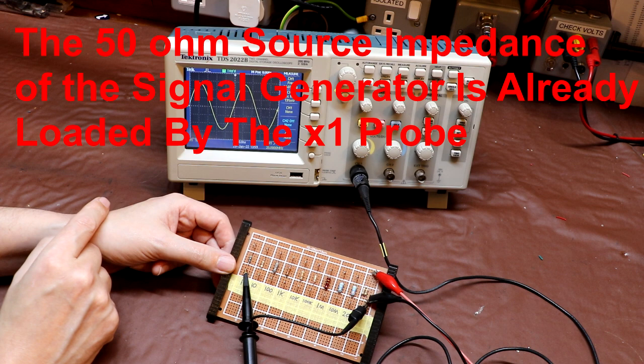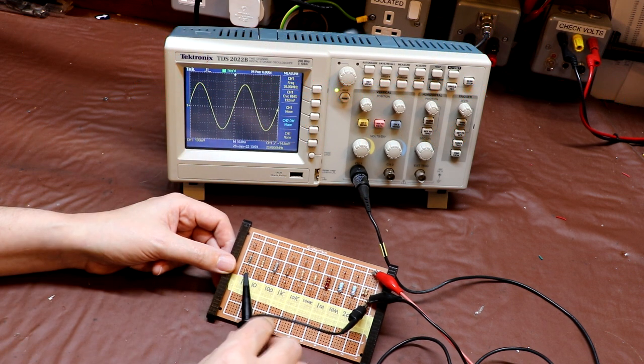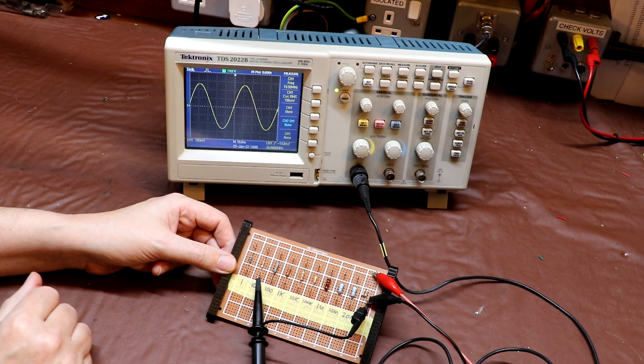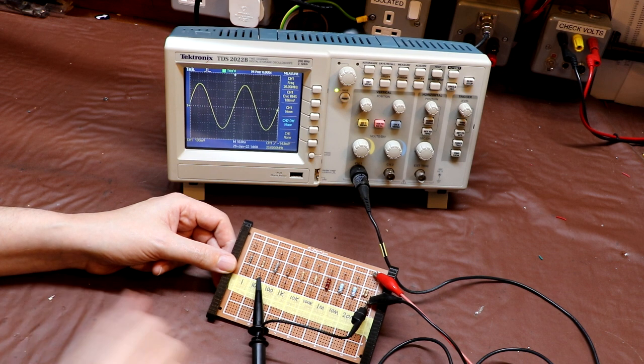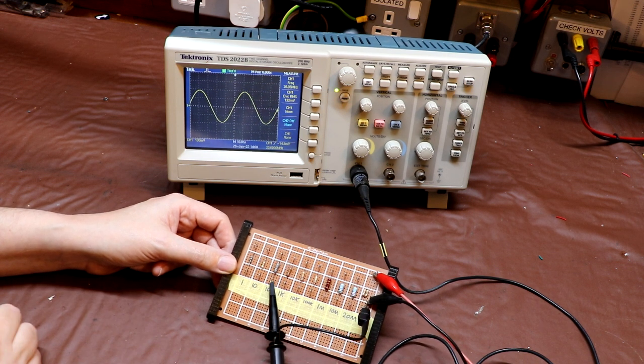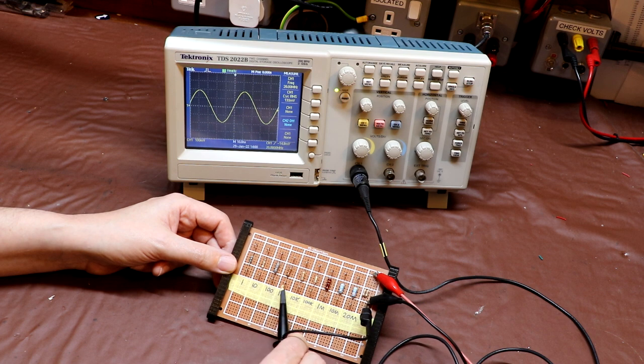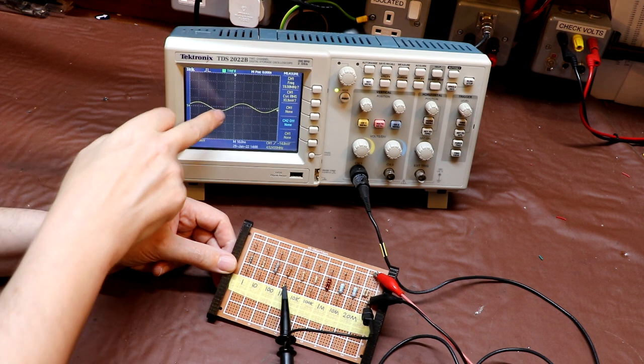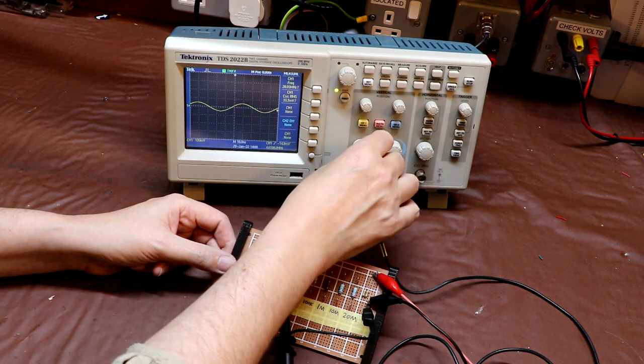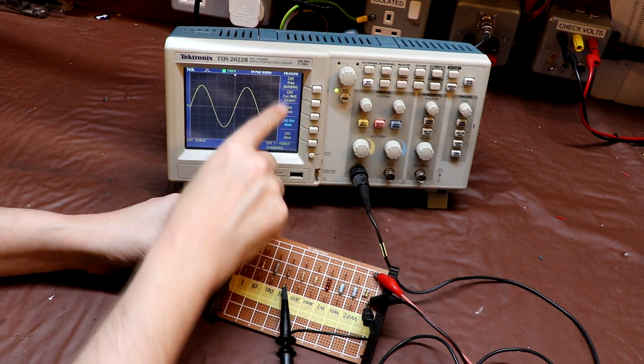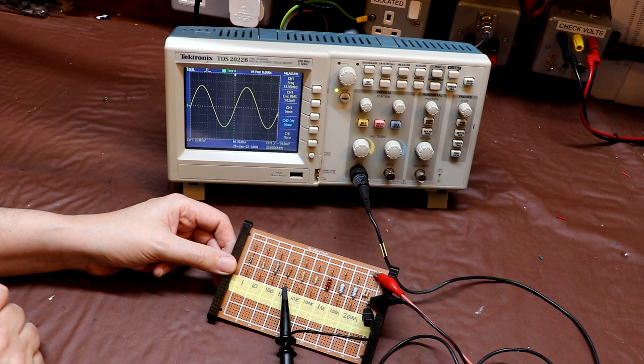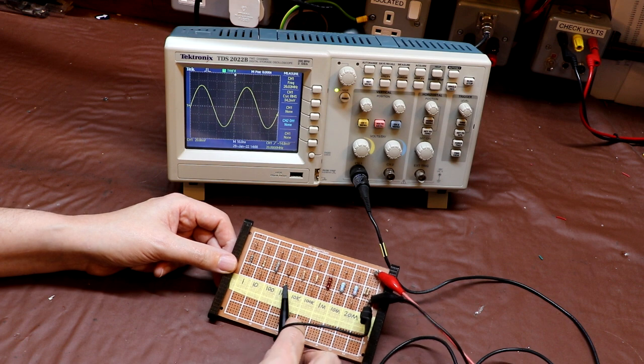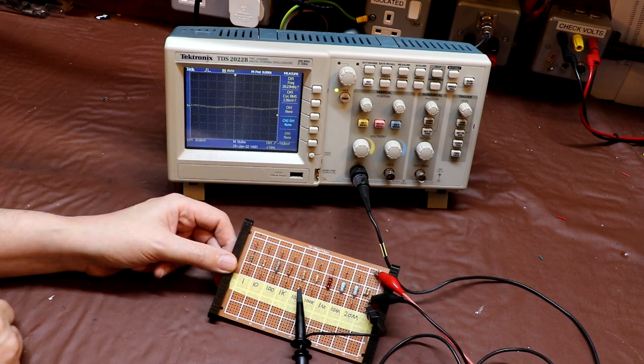Looking at the scope here, it's indicating about 190 millivolts, flicking around slightly. Let's go to the 10 ohm resistor - you can see even with just the 10 ohm resistor in circuit, the voltage has dropped a little to 186 millivolts. Let's go to 100 ohms - quite a significant drop there, now only 132 millivolts. Let's go to 1K - another big drop, we'll have to adjust the sensitivity of the scope. So there's a massive drop - at 1 kilohm we're only at 34 millivolts now. And at 10 kilohms, the signal has pretty much disappeared altogether, or certainly dropped back into the noise.